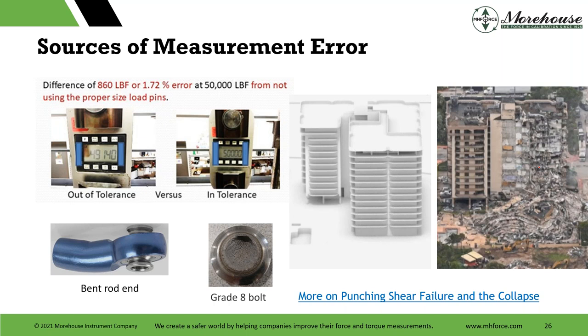Well, it goes into the fact of concrete testing, which comes back to maybe not this one, but several other buildings. When they pour concrete and the concrete's not tested properly, and you use load cells to test the machines that then test the concrete. So if you're off on hardness of adapters, you're off 0.3% with that. You might be off a lot with technicians overshooting test points, and you're doing all this other stuff. You might be off 0.5%. Will that make a difference on the concrete? Maybe. Maybe on what's being tested.